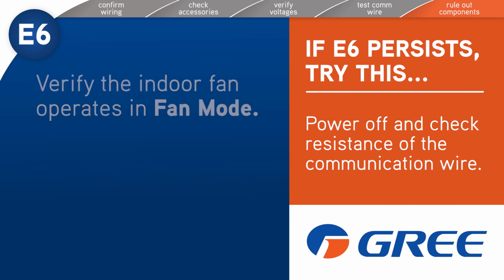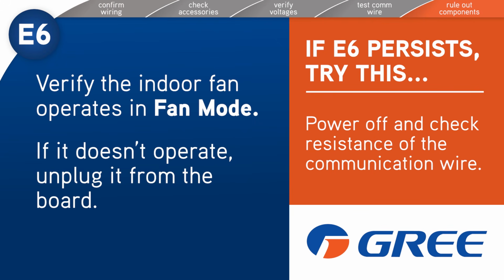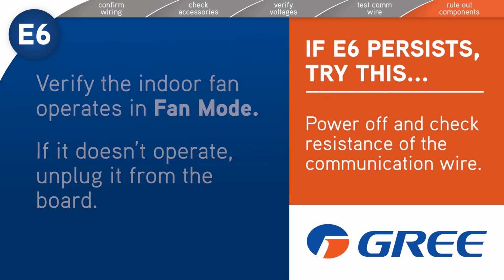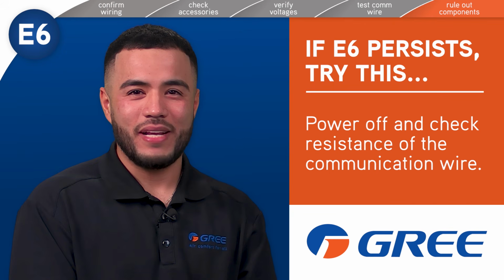Finally, verify the indoor fan operates in fan mode. If it doesn't, unplug it from the board. And if the E6 changes to a fan error, the motor is likely the issue. If everything else checks out, the indoor main board may need replacement.